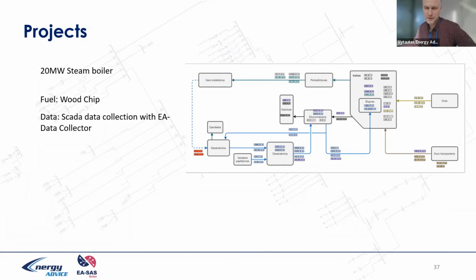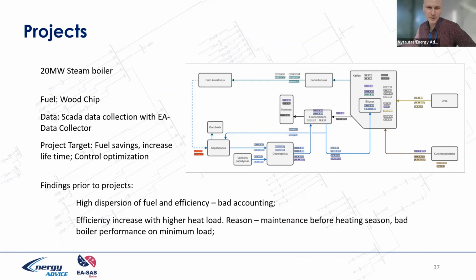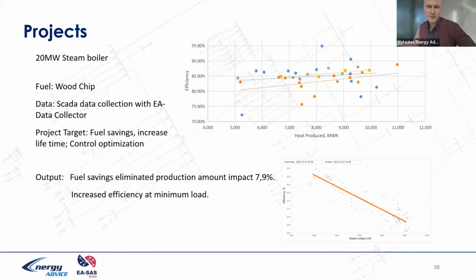Half an hour we spent, coming back from advertisement to issues. A 20 megawatt steam boiler, we installed it. Why did our client choose it? Because we had a bad KPI: efficiency, or production divided by fuel megawatt hours. Here on the top is historical data: heat production is decreasing, efficiency is decreasing. When we started the digital twin, everything went the opposite way. From the EA-SAS picture, fuel savings were near 8% in 1 year, through many dynamics, in an industrial application with steam consumption for paper production. You can imagine paper production is quite a dynamic process.